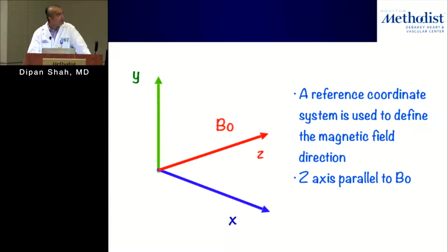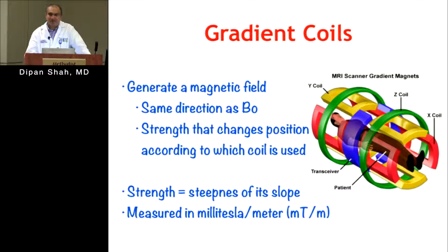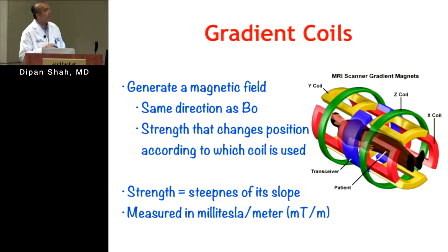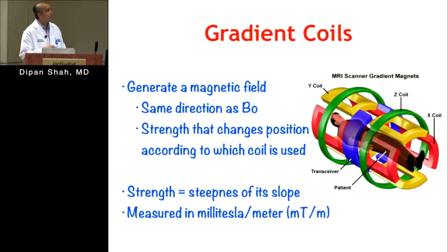Let's go into more detail about gradient coils. The gradient coils are within the MRI system itself. Their purpose is to generate an alteration to the magnetic field. They're aligned in a variety of directions — in the same direction as B-naught, the main magnetic field, but also in other directions. You essentially have a gradient in all three directions of the XYZ coordinate system. The strength of the gradient is measured as the steepness of the slope in millitesla per meter.